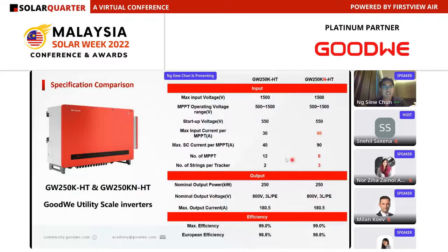So like I mentioned earlier, we have two models for 250K, the 250K and 250K NHT. The difference is not so much on the DC side. The start-up voltage, as we can see, is similar. The maximum input voltage is up to 1,500 VDC, typical for utility scale projects. But the difference is the input current. The NHT would have 6 MPPT, 3 strings per MPPT, and 20 amps per string. And for the K series, without the N, that would be 12 MPPTs with 2 strings per tracker, and each string will support up to 15 amps.